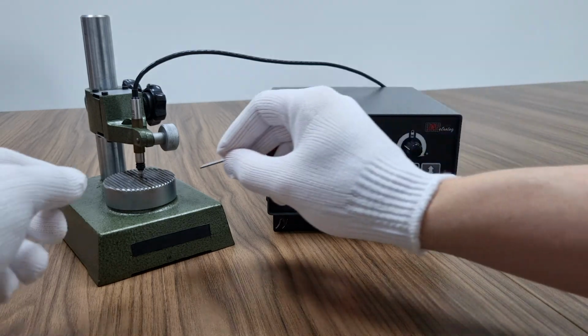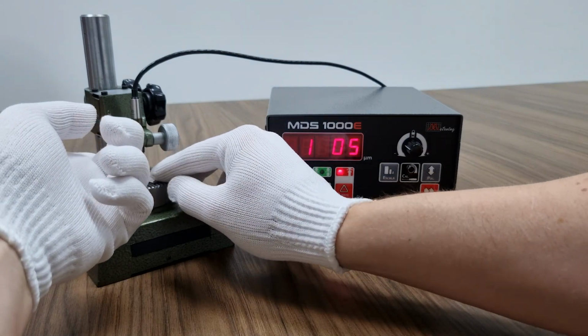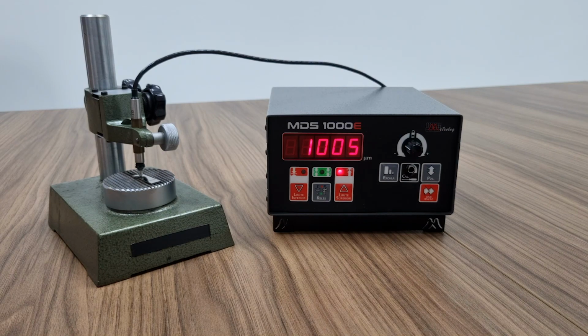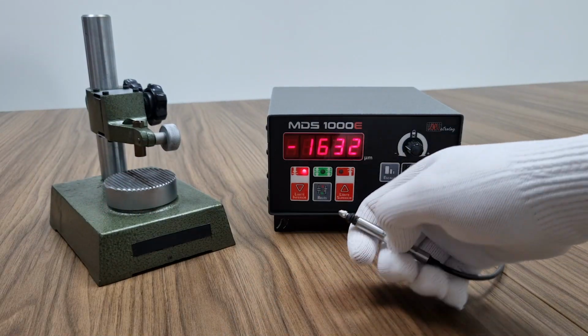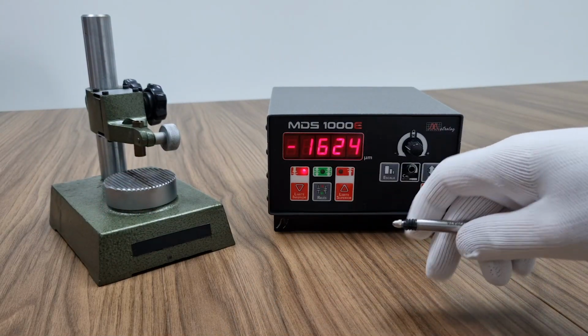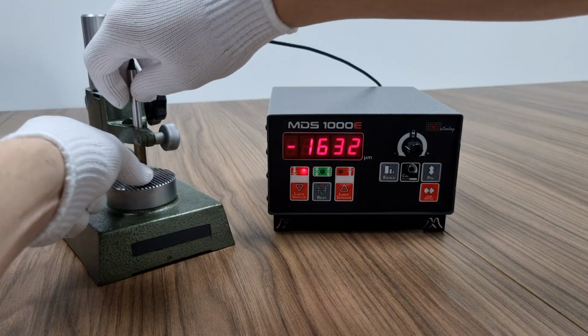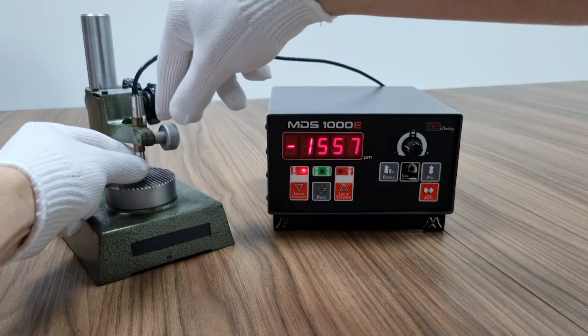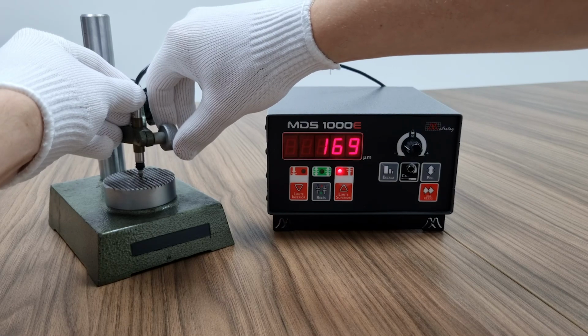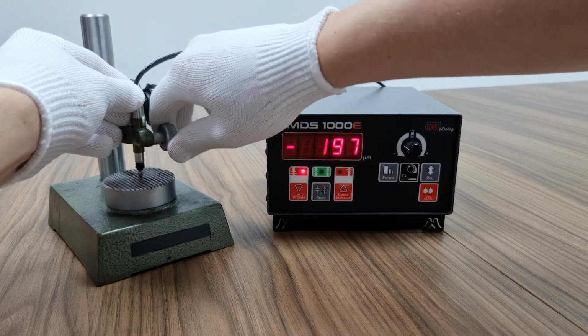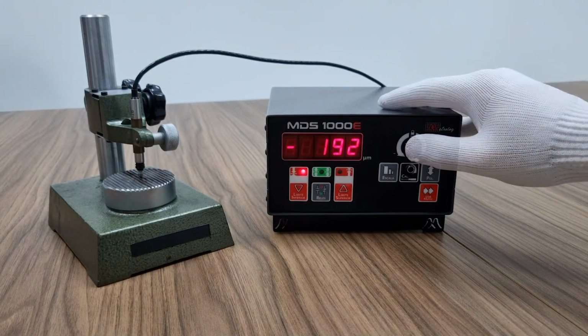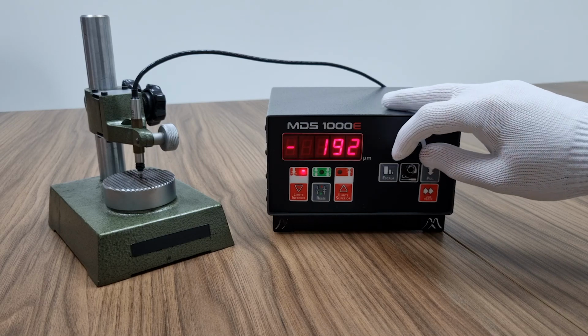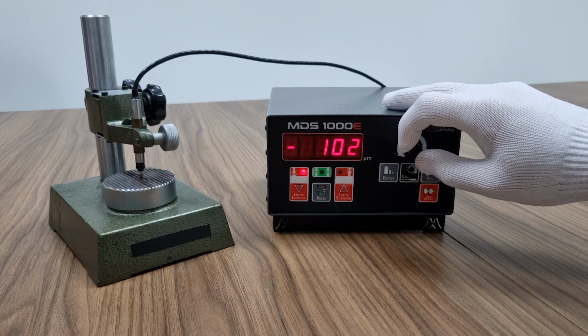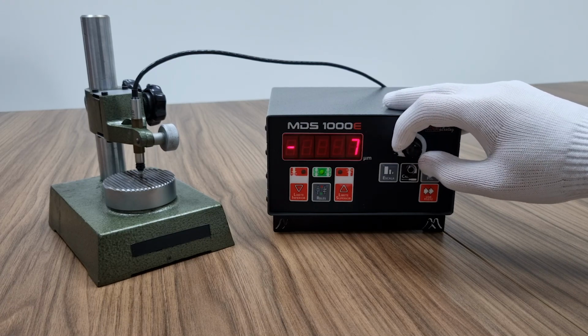For calibration, it is recommended to apply a displacement between 20 and 80% of the total measuring travel of the sensor. The useful mechanical limits of the sensor should be observed to avoid working in the pre- and post-stroke region of the plunger. Measurement. Typically, the sensor should be fixed to the measuring device, observing the correct working position of the plunger. After fixing the sensor, the zero adjustment must be carried out with the aid of a calibration standard or reference face. The equipment is then ready for dimensional inspection of new parts.